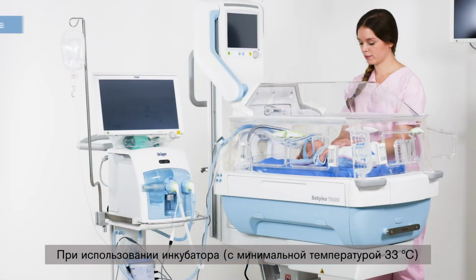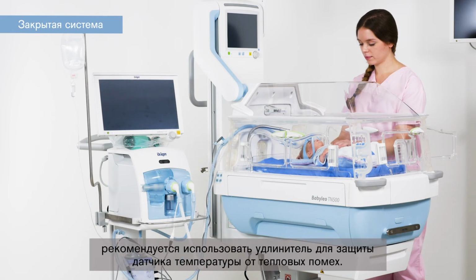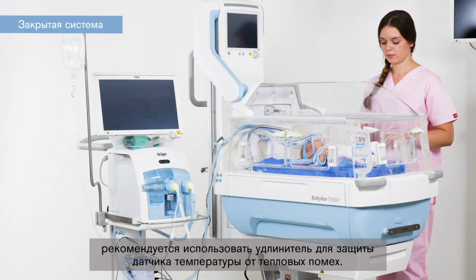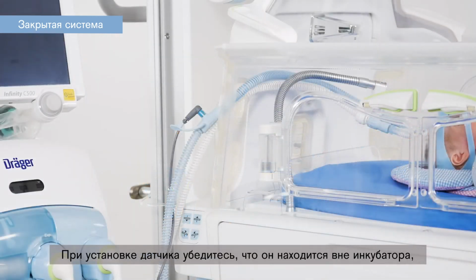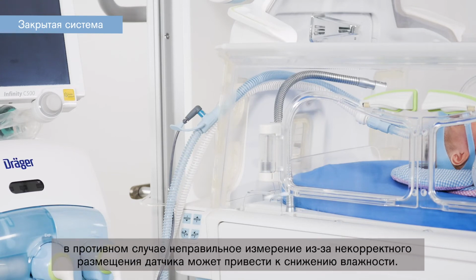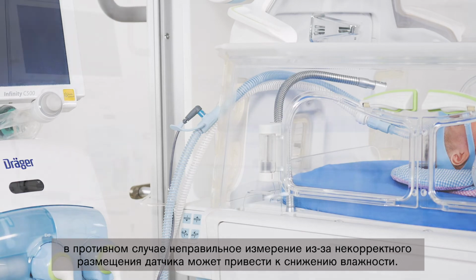When using an incubator with a minimum temperature of 33 degrees Celsius, it is advisable to use an extension to protect the temperature sensor from thermal interference. When positioning the sensor, make sure that it's placed outside the incubator. Otherwise, an incorrect measurement due to thermal interference may lead to a reduction in humidification.